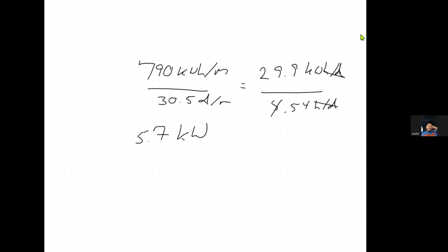Mm-hmm. All right. But it's not going to be 100% efficient. So now I have to divide it by the efficiency of the system. Well, we went through that whole derate process, and we decided with this array, it's about 8.5% inefficient, which would mean that it's about 91.5% efficient. So the derate factor is going to be 0.915. That's just 91.5% decimalized. So at this point, you divide.